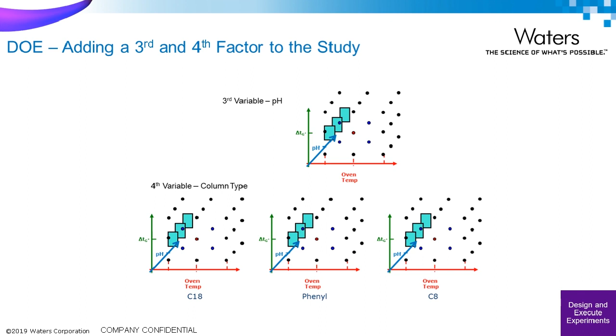When we assessed the proposed EP monograph method that the USP was looking at harmonizing, we noticed 3 primary parameters that we felt would be a problem without even any experimentation. And that was the oven temperature of 20 degrees. The method also had an ion pairing agent, and as I mentioned earlier, had a multi-step gradient, which had 3 steps right around the vicinity of the API. In addition, very few of the impurities next to the API separated very well. So just looking at the method from an evaluation standpoint, these method parameters pose significant risk to being able to transfer the method.